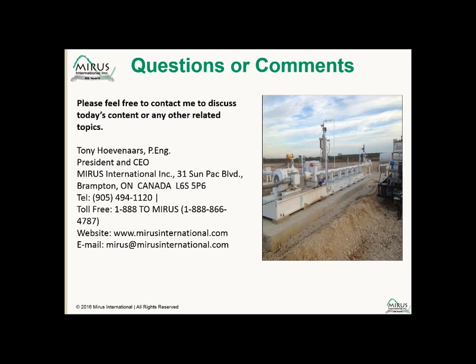How do you use your filters to reduce harmonic content for a generator that supplies IT servers as a backup? It depends how the servers are connected. Some servers might be connected phase to phase. Other servers might be connected phase to neutral. If they're connected phase to neutral, they're going to introduce 3rd as well as 5th, 7th and 9th harmonics. So a different type of filtration and equipment would be recommended in that application, but it can still be every bit as effective as the wide spectrum harmonic filters that we use on variable speed drive applications. That is something we could follow up with you on, and I'm sure we can come up with a very effective solution.